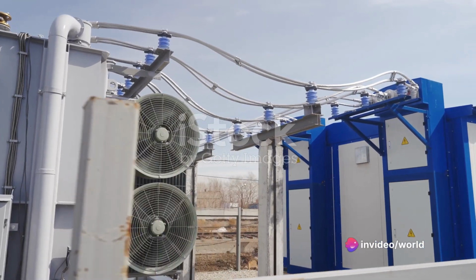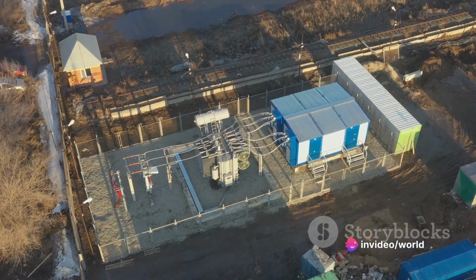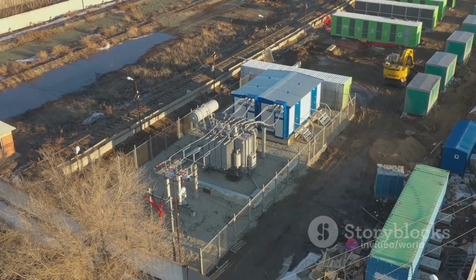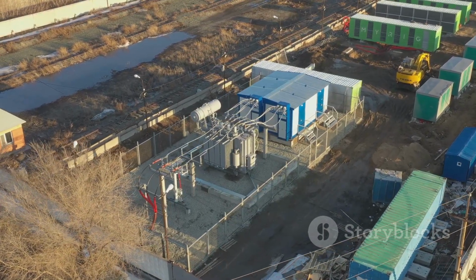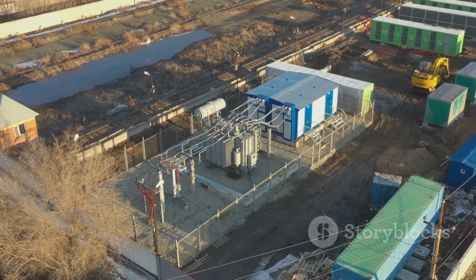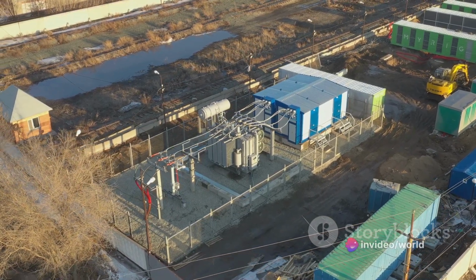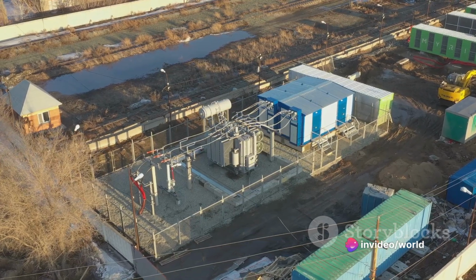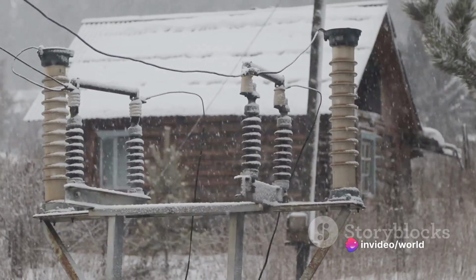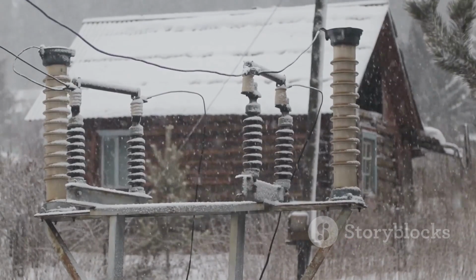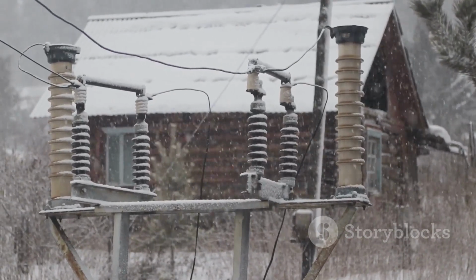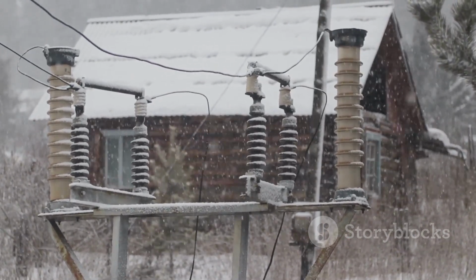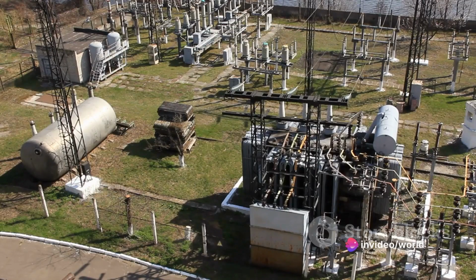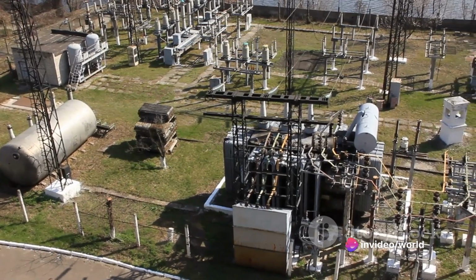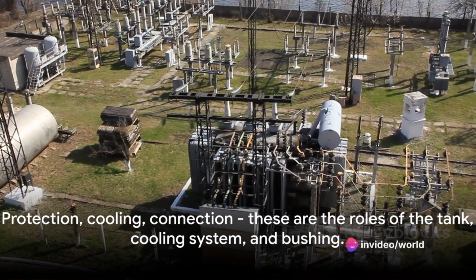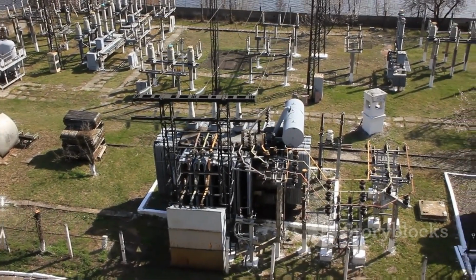Now let's talk about heat. Transformers generate heat due to losses in the core and windings. This is where the cooling system steps in. Whether it's fans, radiators, or oil circulation systems, these cooling mechanisms work relentlessly to dissipate heat, keeping the transformer's temperature within safe limits. The last piece of the puzzle is the bushing. These insulating devices connect the transformer windings to external circuits. They maintain electrical isolation, provide mechanical support, and seal out moisture or contaminants. Protection, cooling, connection, these are the roles of the tank, cooling system, and bushing.